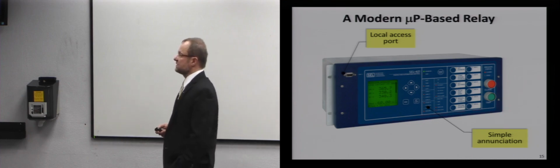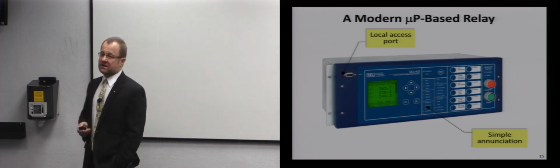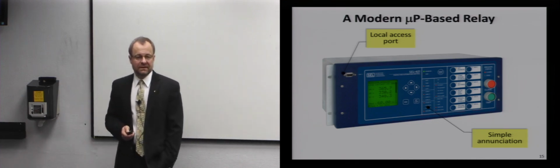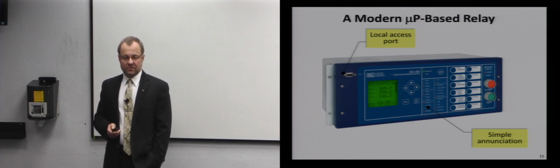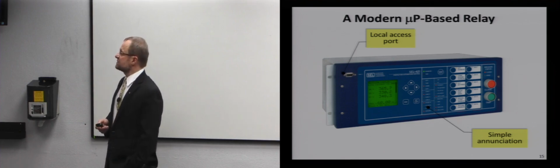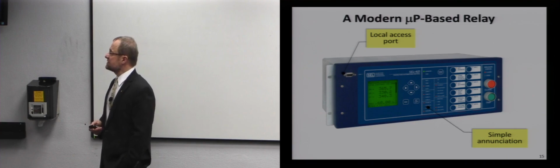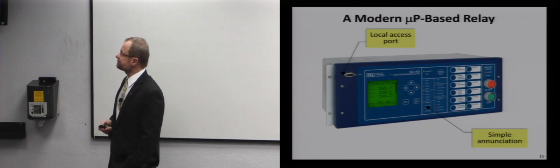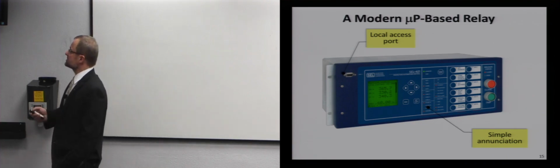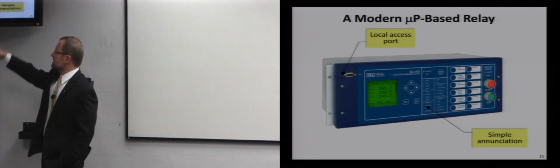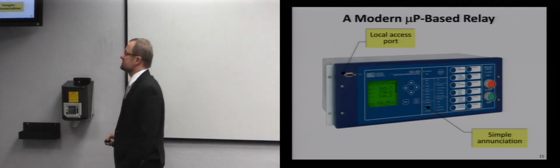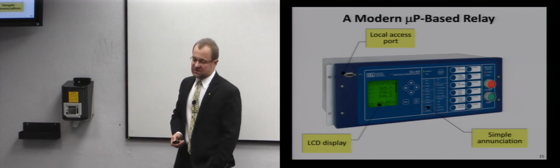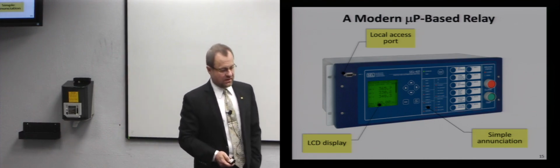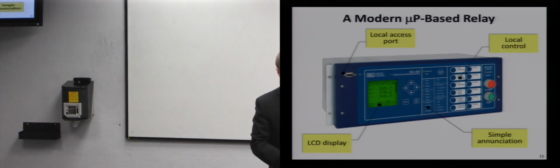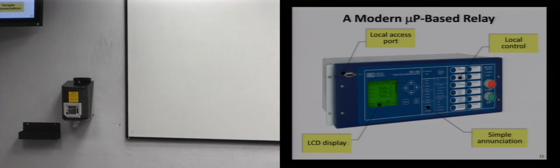They could always connect the laptop to that port and get all the information from the relay, including a recording of what happened with proper timestamps and what have you. But the first layer of communication with a human is the simple LED annunciation. You have an LCD display to display metering and alarms and so on. Local control: you could change setting groups, and you could close and trip the breaker.